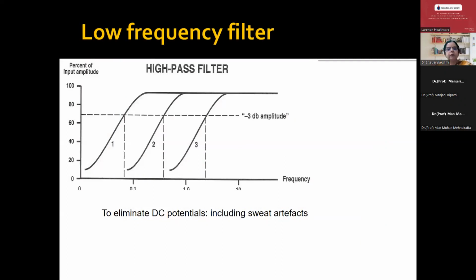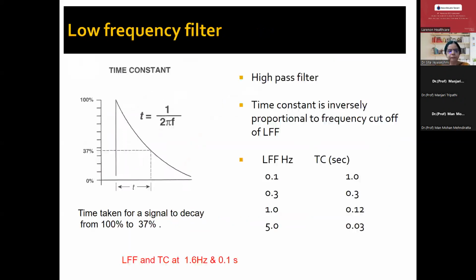The second one is the low frequency filter. The low frequency filter is important to eliminate the direct current potentials, especially the sweat artifacts. The low frequency filter is also known as the high pass filter.